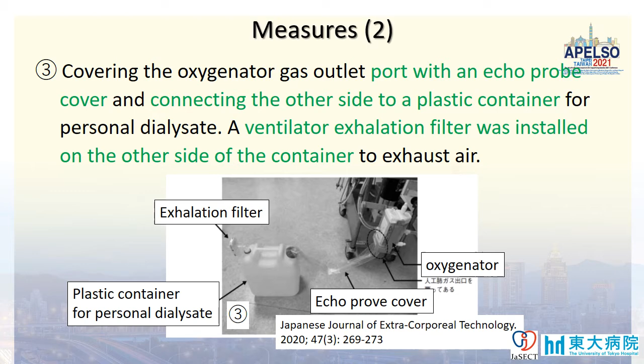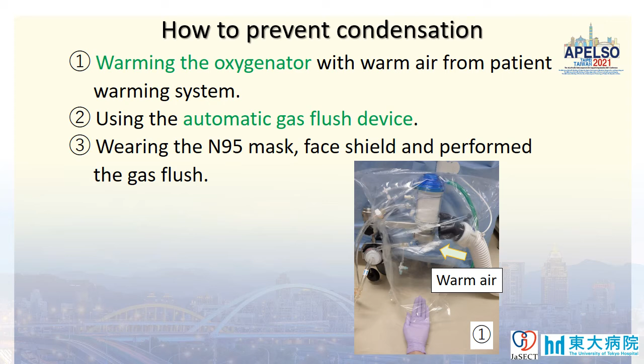I introduced how to prevent condensation in our journal on this slide. There are three types of ways. First, the method of warming an oxygenator with warm air from a patient warming system. Second, using the automatic gas flush device. Third, staff put on the N95 mask and face shield and perform the gas flush.